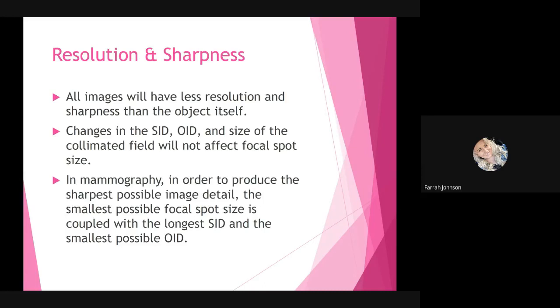In mammography, in order to produce the sharpest possible image detail, the smallest possible focal spot size is coupled with the longest SID and the smallest possible OID. So we want a small focal spot so we get great detail. We want a longer SID, and we want the smallest possible OID. Okay, and that is all I have for you for Chapter 5.